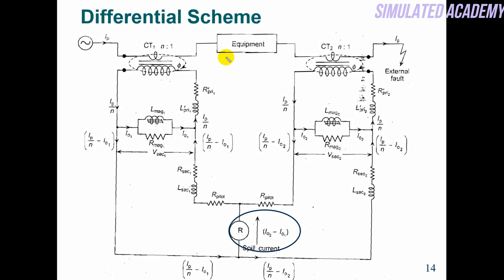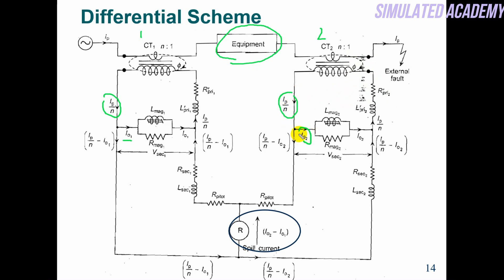For the differential protection equivalent circuit: the equipment to be protected has two CTs — CT1 with primary and secondary sides, primary impedance, and secondary-referred impedance. Current i_not1 passes through the magnetization branch. Primary current referred to secondary is ip/n, and ip/n minus i_not1 flows through the relay side. On the secondary side, ip/n flows, and i_not2 passes through the magnetization branch, leaving ip/n minus i_not2 for the relay. The spill current is i_not2 minus i_not1 — this is the current that passes through the relay.